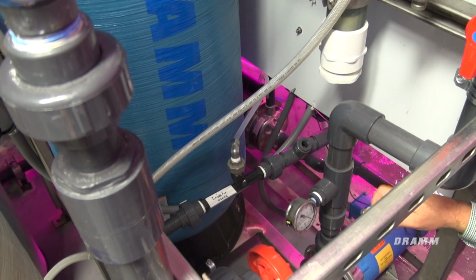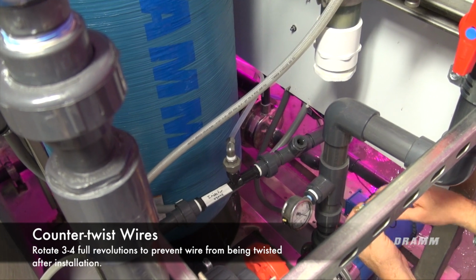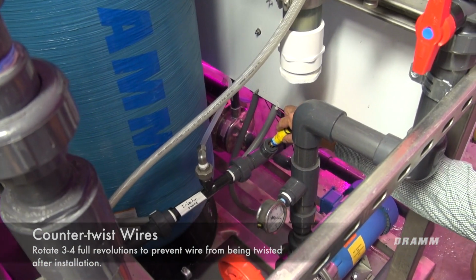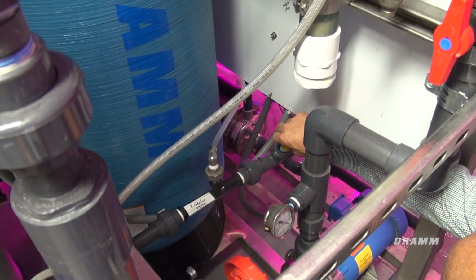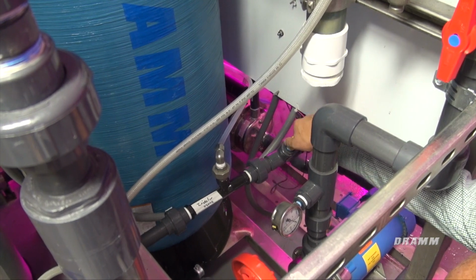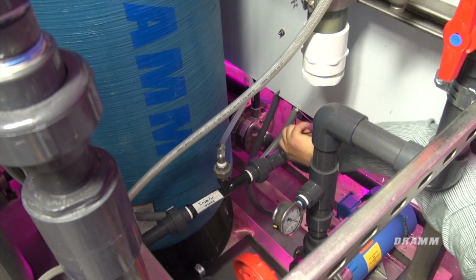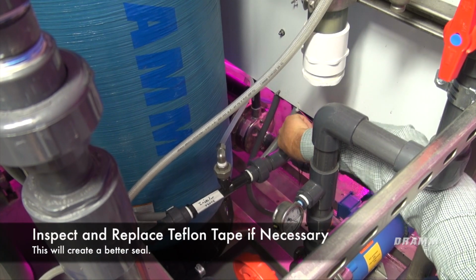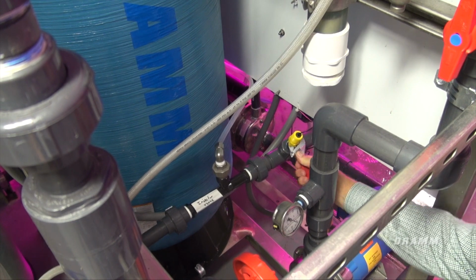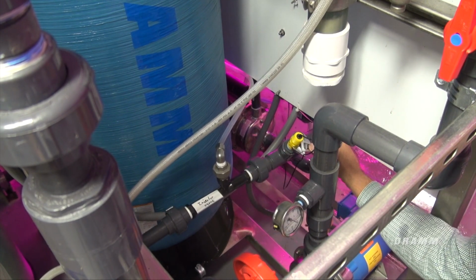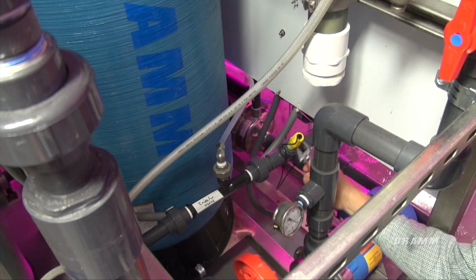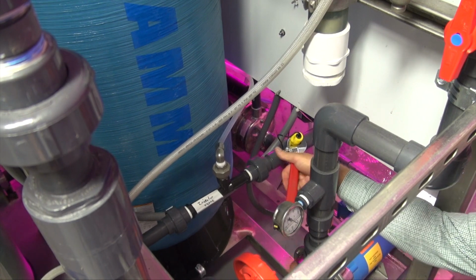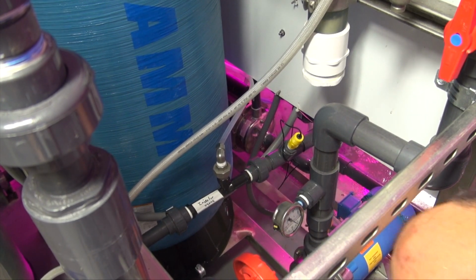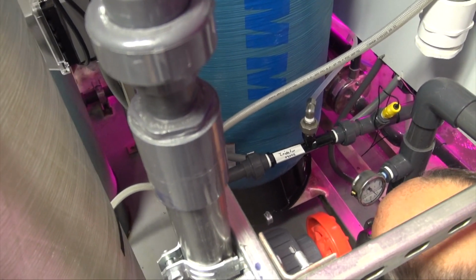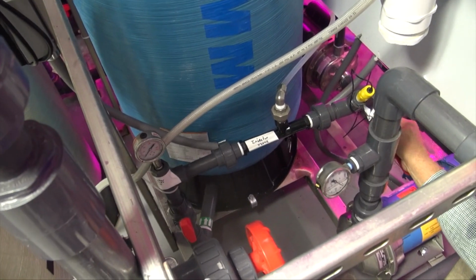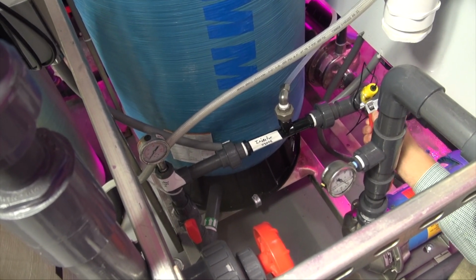Alright, we're going to reinstall this. I always counter twist them before I start reinstalling them so that the cable doesn't get twisted up. Put it in, making sure that we don't touch the tip of the probe up against the pipe. Tighten it reasonably tight by hand. Put the wrench on it and make sure that you don't over secure it. What we'll do is get it in just snug, and then we'll turn the water back on and check for leaks, and then we'll snug that down. If we see a leak, we'll snug it down a little bit more, and you're good to go.